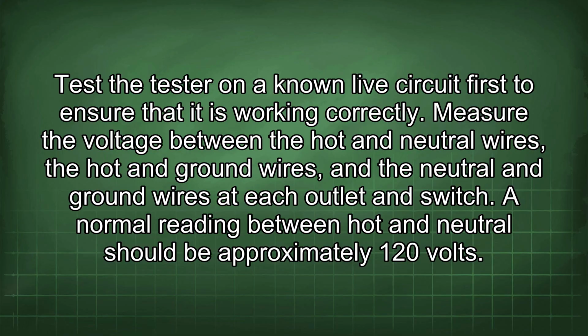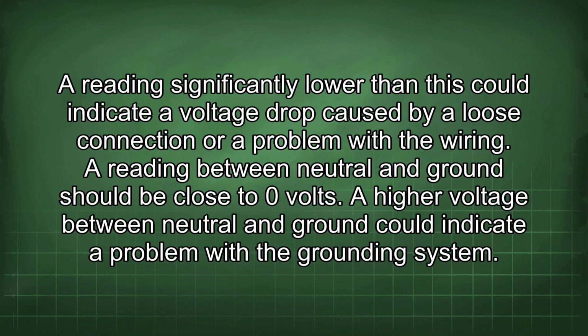A normal reading between hot and neutral should be approximately 120 volts. A reading significantly lower than this could indicate a voltage drop caused by a loose connection or a problem with the wiring. A reading between neutral and ground should be close to 0 volts. A higher voltage between neutral and ground could indicate a problem with the grounding system.